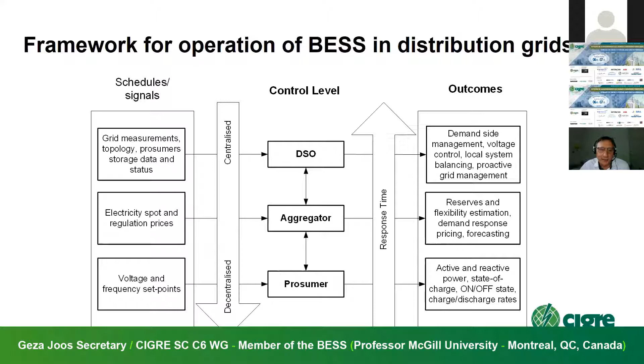Planning considerations. I will go through this very briefly because I'm running out of time. You will have the slides so you can have a look at them. And if you have any questions, feel free to send them to me. As I mentioned, and this is just a summary, the battery energy system has a steady state operation like any device and a transient operation. The steady state operation is defined by the inverter and by the stored energy, and these are the things I mentioned before. Inverter kVA rating, efficiency. By the way, efficiency and losses are extremely important, and one of the big issues with flow batteries is the important losses, store and retrieve.